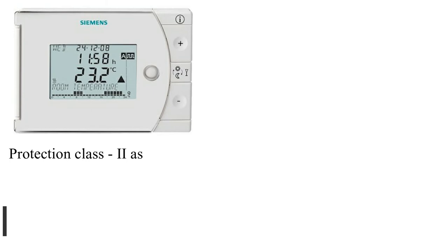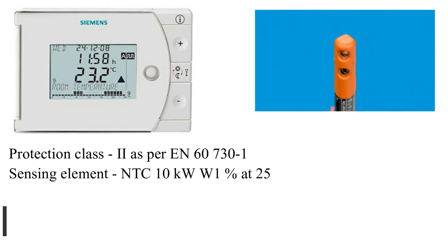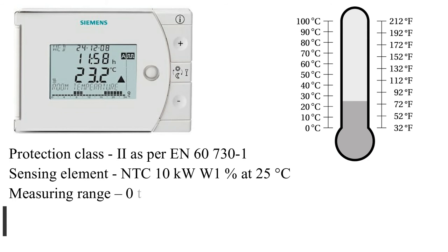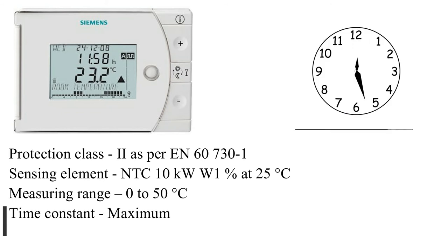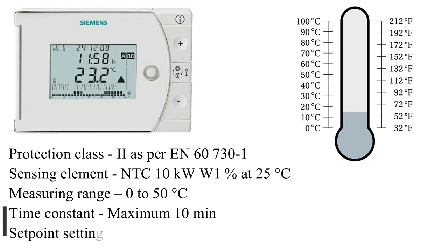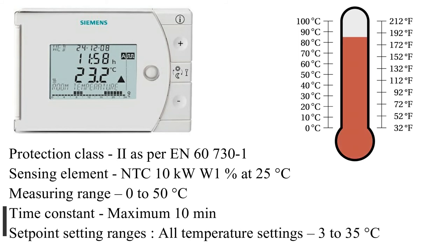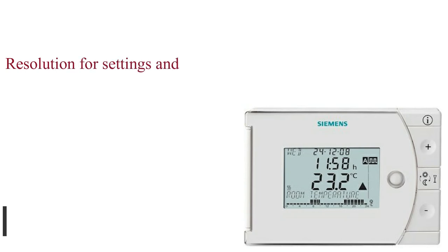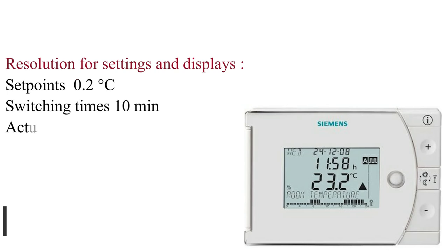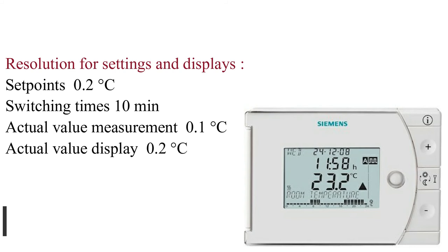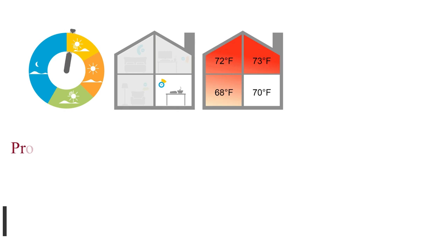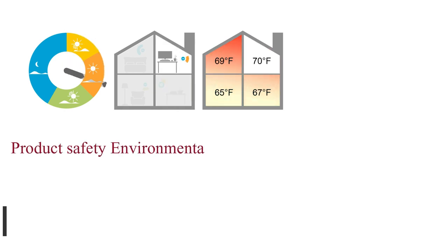Protection class 2 as per EN 60730. Sensing element: NTC 10 kilohms ±1% at 25°C. Measuring range: 0 to 50°C. Time constant: maximum 10 minutes. Set point setting ranges — all temperature settings: 3 to 35°C. Resolution for settings and display setpoints: 0.2°C. Switching times: 10 minutes. Actual value measurement: 0.1°C.